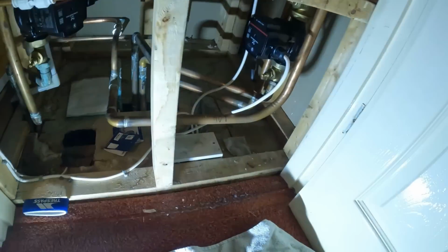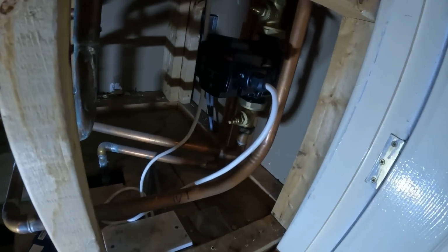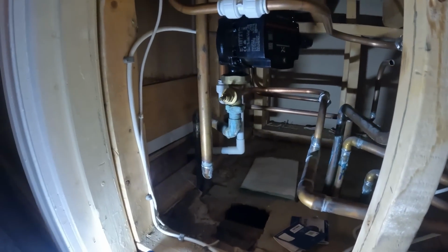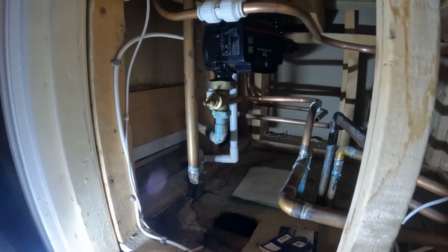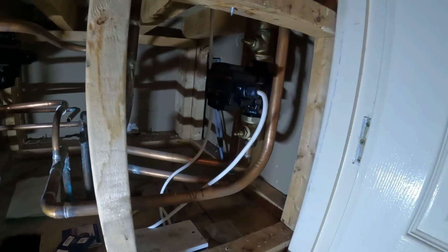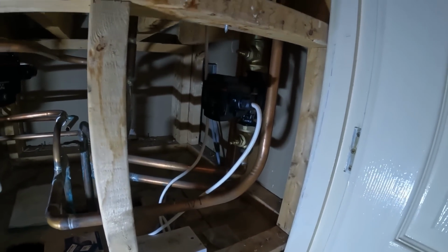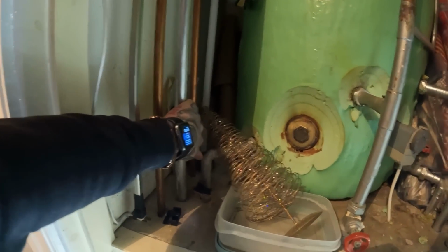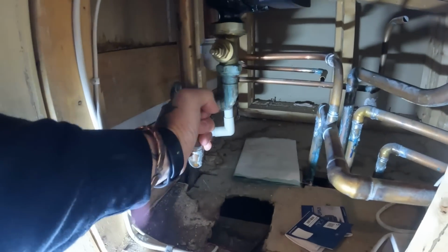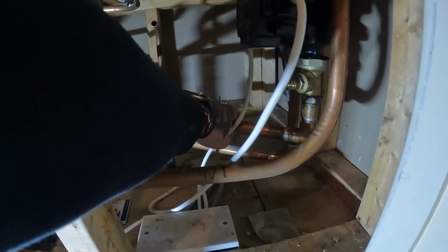So you've got a coil that separates the two, cold in, hot out. Underneath here you have two pumps. Let's get a torch so we can see. You've got a pump on the right hand side and a pump on the left. That pump on the left drags the heat from the boiler to warm up the water in the tank, and the pump on the right takes water from the tank when you request the radiators to get warm, pulling water around the radiator circuit and back to the tank. I hope that makes sense, because it doesn't to me right now.